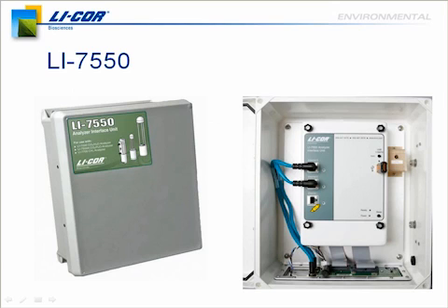That Ethernet connectivity is a significant step forward because now, if your site is networked, you can remotely access the instrument, monitor its performance, and even retrieve data from the instrument via the network without having to visit the site. So that's another step ahead when you've got remote field sites and instruments positioned all over the world. Now you can access them very quickly, make sure they're performing properly, collect your data, and move on without having to spend a day going out to the field site.